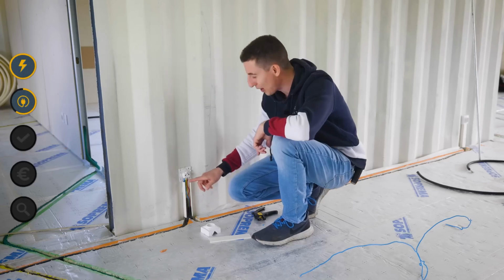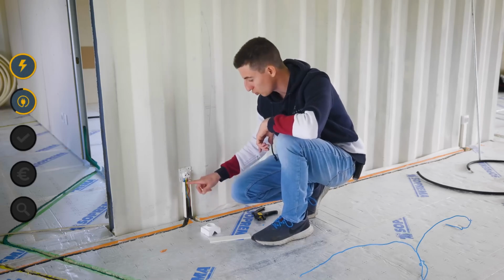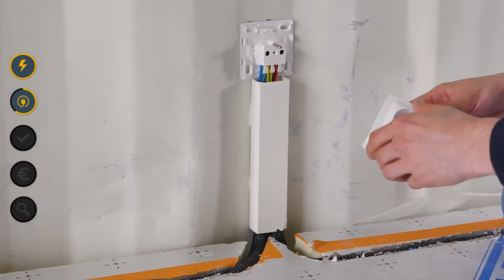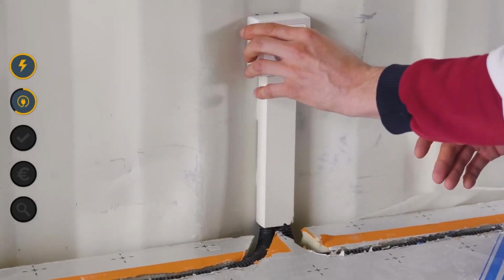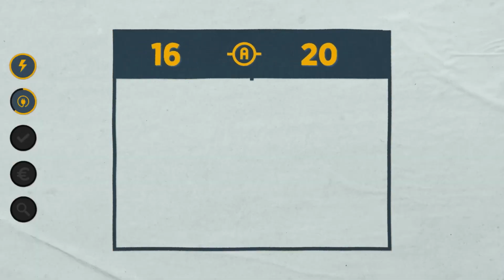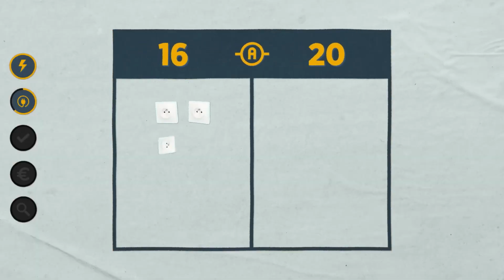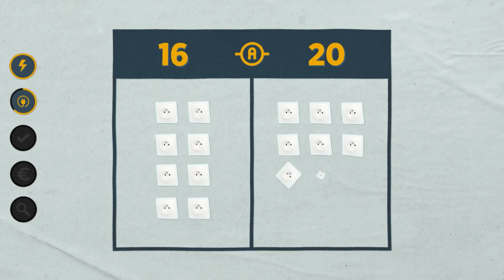Then we come out of the socket with 3 other wires that go back into another sheath, which will go to power the other sockets of this circuit, according to the NFC 15-100. On a 16A circuit breaker, you can bridge up to 8 power outlets, and on a 20A circuit breaker, up to 12.